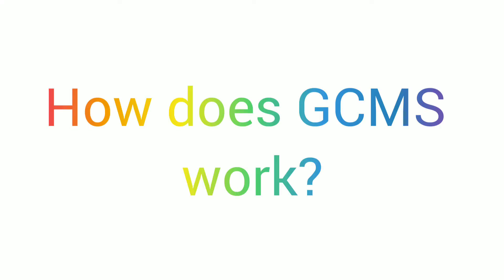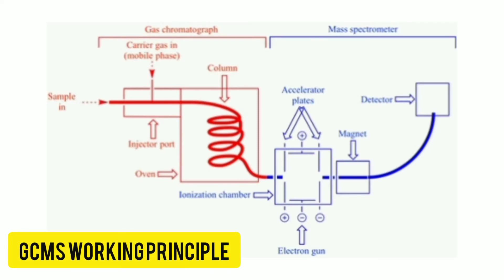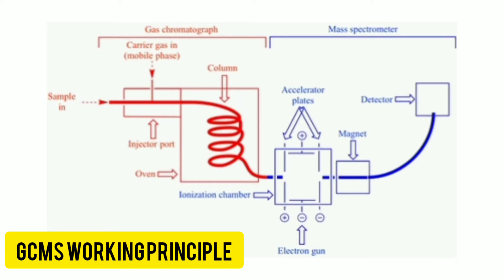How does GC-MS work? Samples are introduced into the GC through a heated injector. The sample gets vaporized at a high temperature. Different compounds are separated when they pass through a column depending on their molecular mass and polarity. The separated compounds sequentially enter the MS via a heat transfer region.